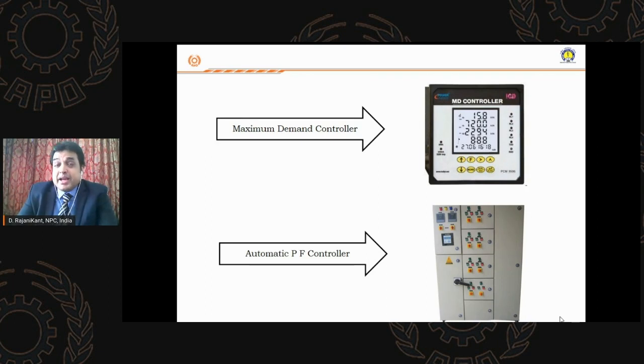And added to that, if your distribution company selling you electricity is charging on a kilowatt hour basis, and you are not maintaining a power factor of at least 0.9, there may even be a penalty. That also depends upon the country they belong to, and the state or province or the distribution company which is selling the power. But normally, a distribution company will levy a penalty on an SME or any company having a very low power factor.